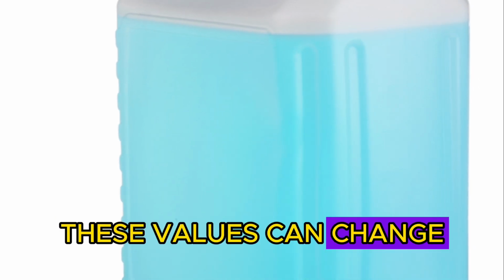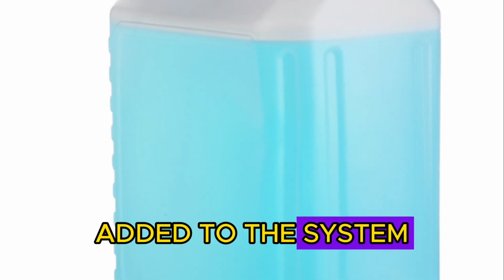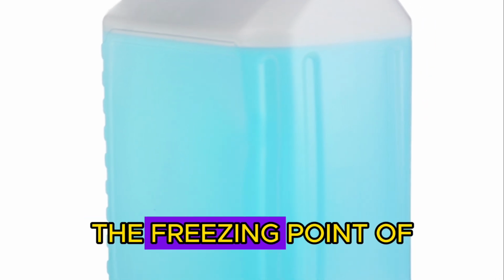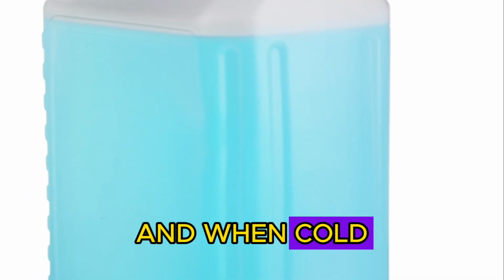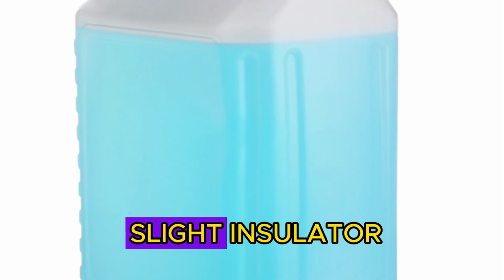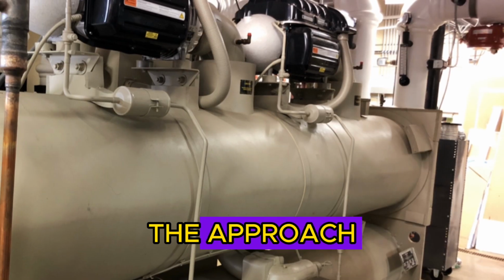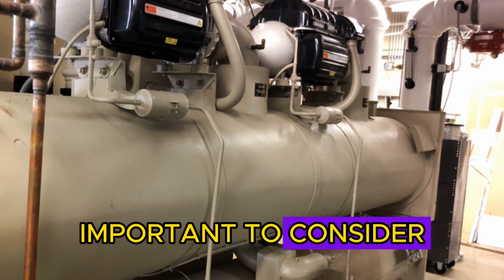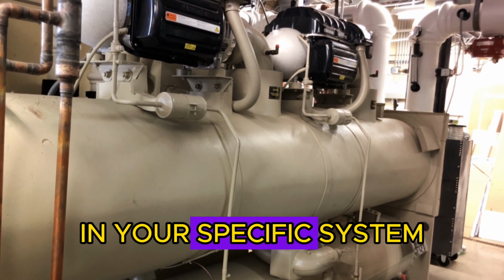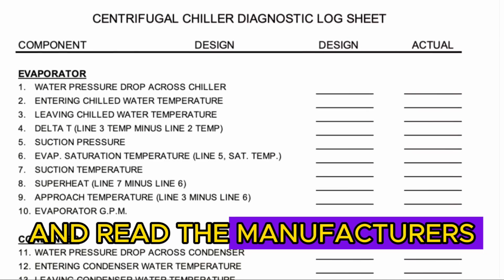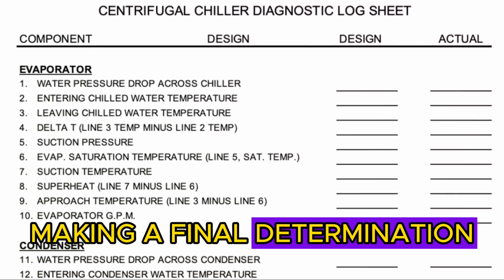These values can change if glycol is added to the system. Glycol lowers the freezing point of the water, and when cold, it contracts and acts as a slight insulator, which can alter the approach. It's always important to consider all the factors at play in your specific system and read the manufacturer's data before making a final determination.